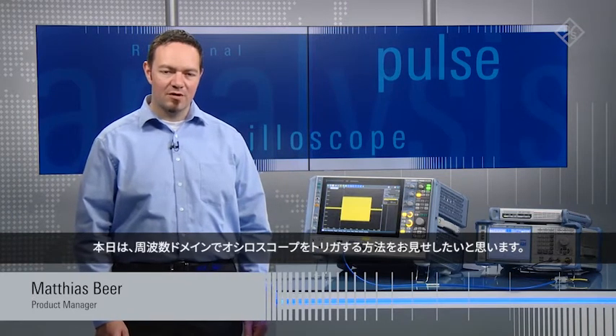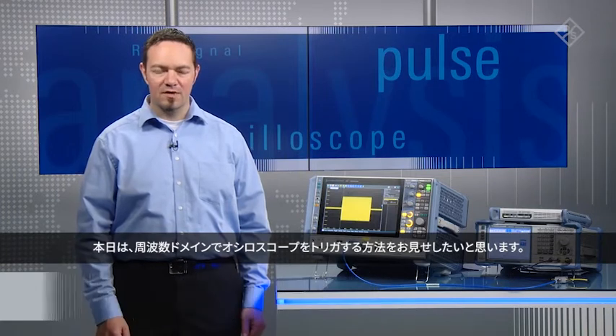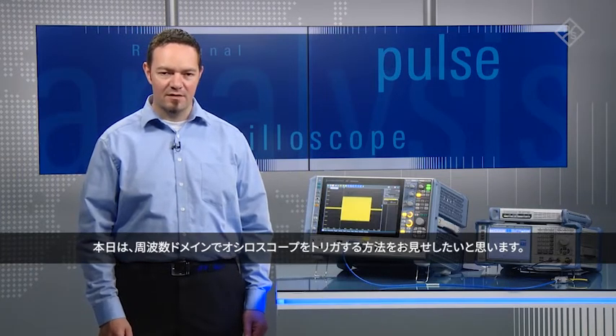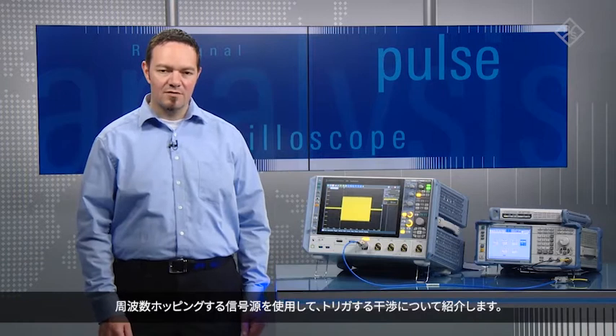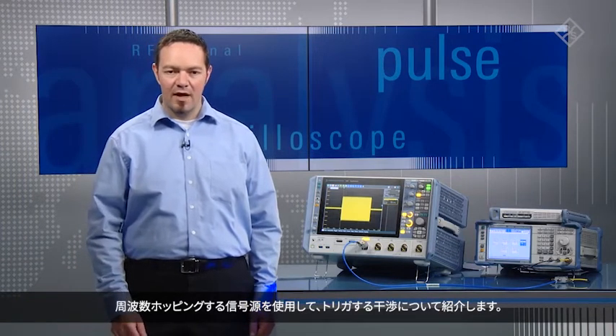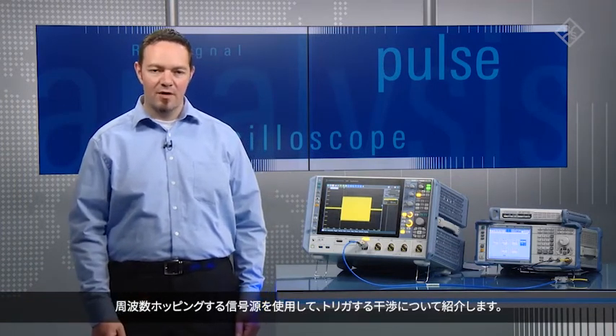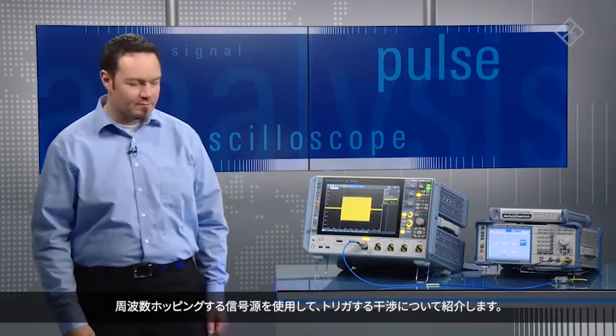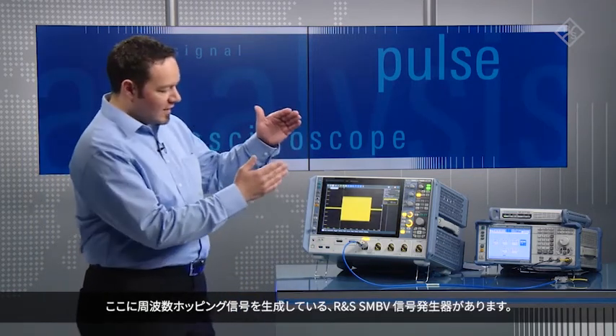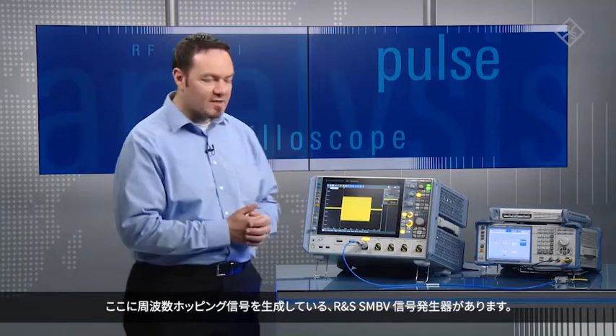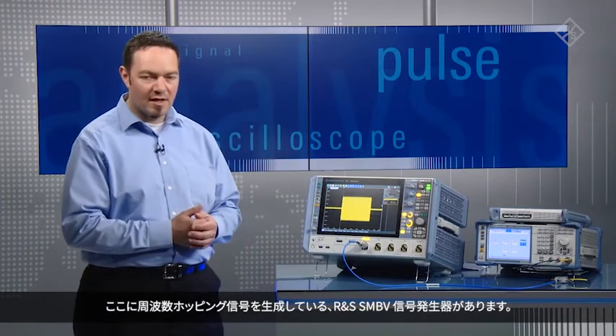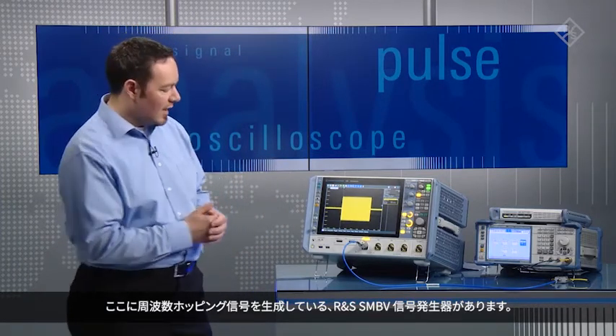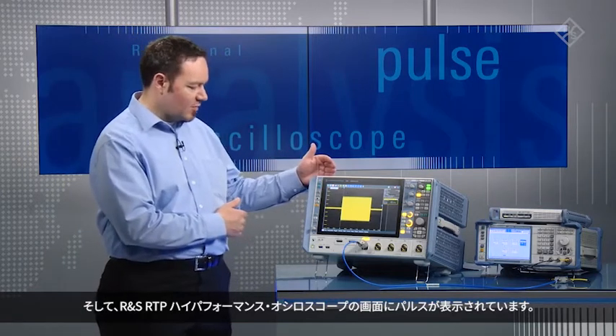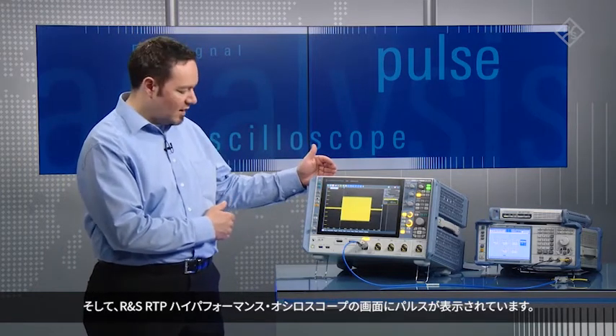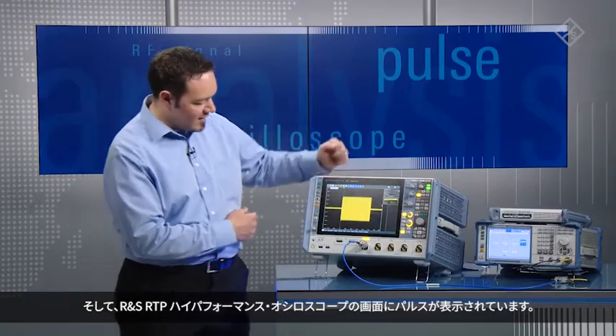Today I would like to show you how you can trigger a Rohde & Schwarz oscilloscope in frequency domain. To do this, we are using a frequency hopping scenario, and we will introduce an interferer which we use as trigger source. We have here a signal generator from Rohde & Schwarz, an SMBV, which is generating our frequency hopping scenario. And we have the oscilloscope, a high performance RTP instrument, where we see already the pulse.